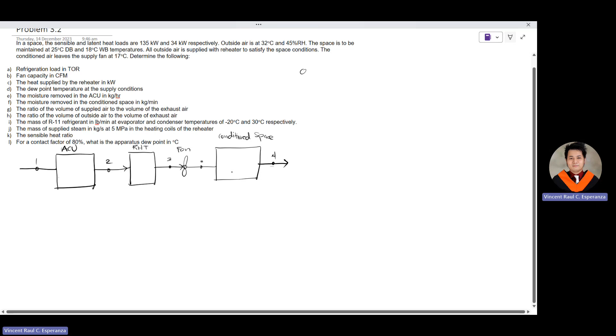Outside air at 32°C, so the dry bulb temperature at point 1 is 32°C, and the RH at point 1 is 45%. The space to be maintained, meaning the conditioned space, has a dry bulb temperature at point 4 of 25°C and a wet bulb temperature at point 4 of 18°C.